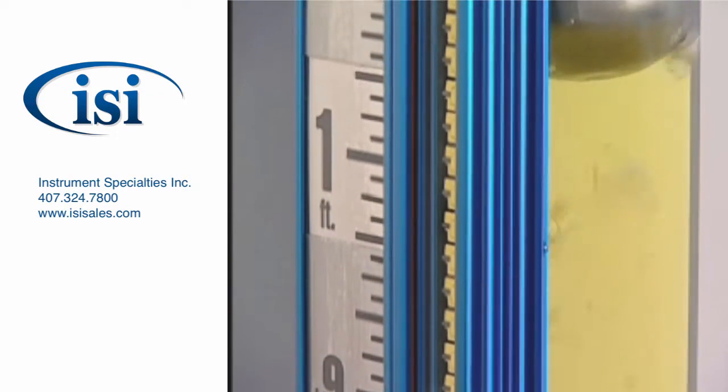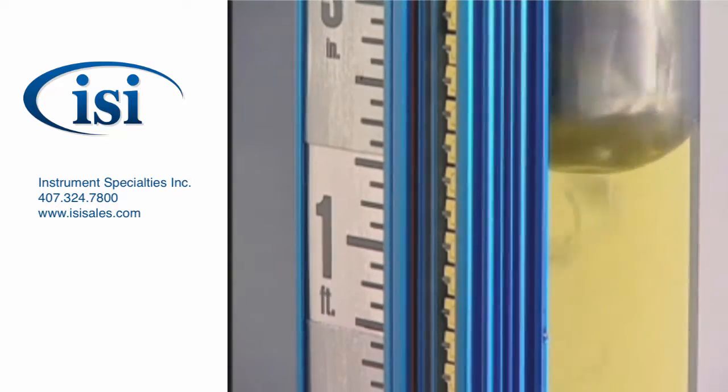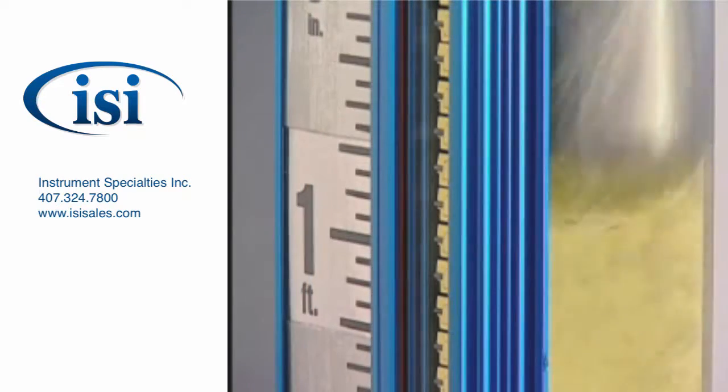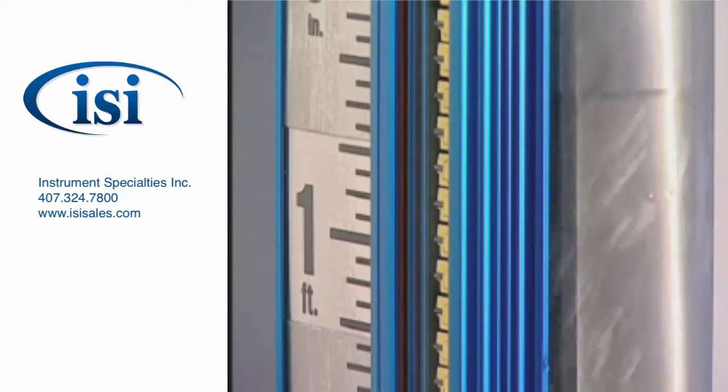Entrained gases from the boiling rise and collect under the float, reducing its buoyancy. This boiling fluid can sink not only your float, but any hope of getting an accurate level reading.